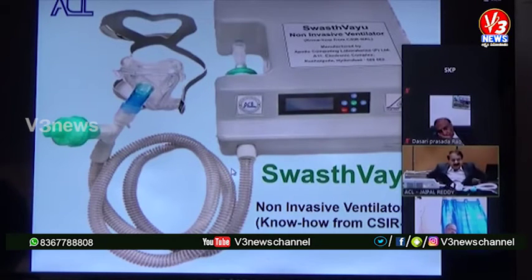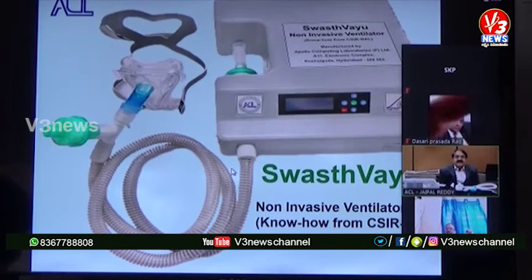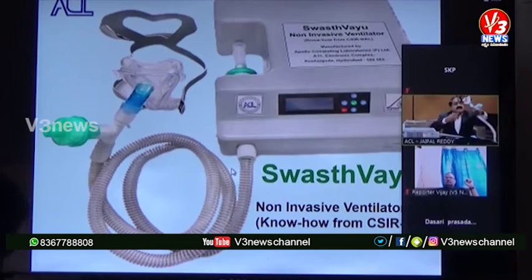In the spontaneous mode, the machine is going to synchronize with the patient's breathing. The patient is breathing at a certain rhythm, a certain rate. The machine will synchronize with it and pump pressurized air along with the oxygen. So there is an oxygen inlet here. You connect the oxygen here, and you can connect the oxygen up to 15 to 17 liters per minute.